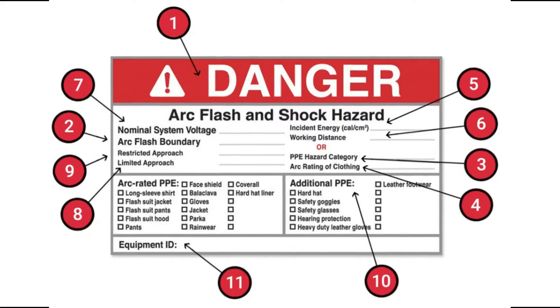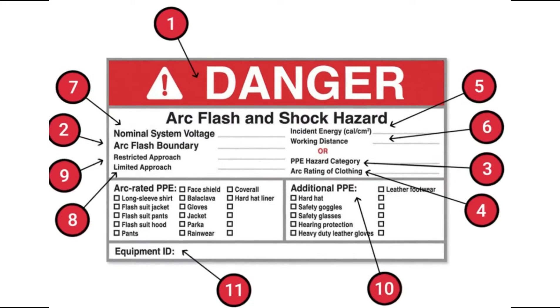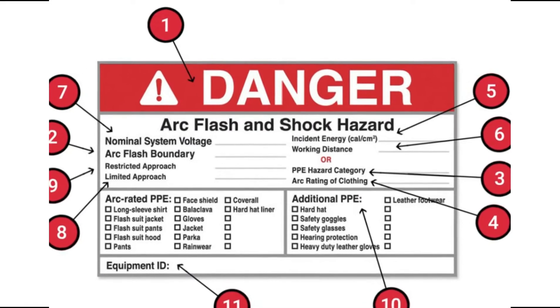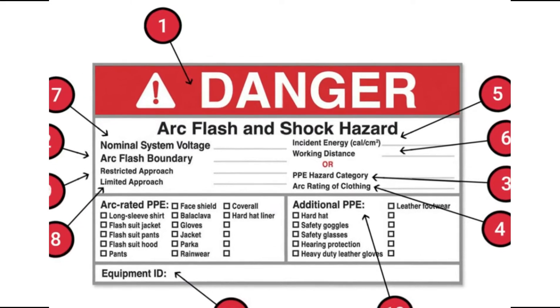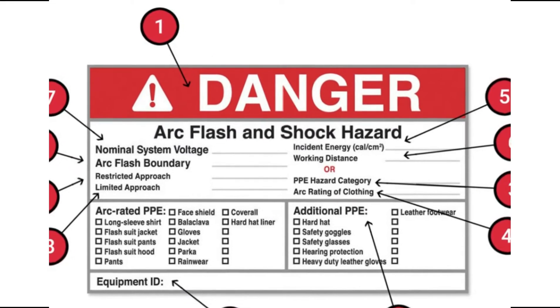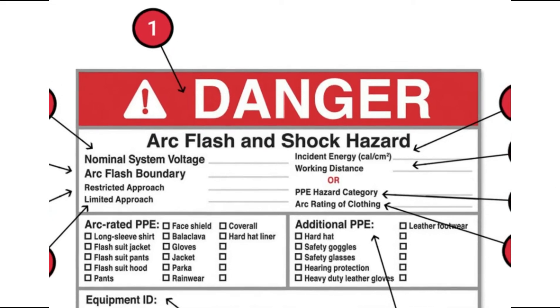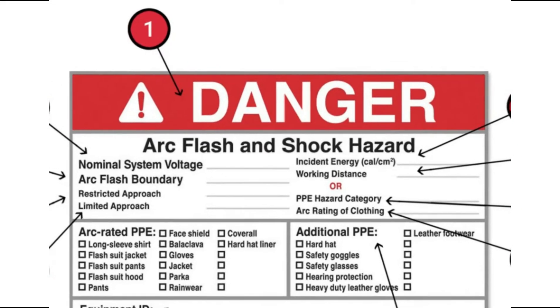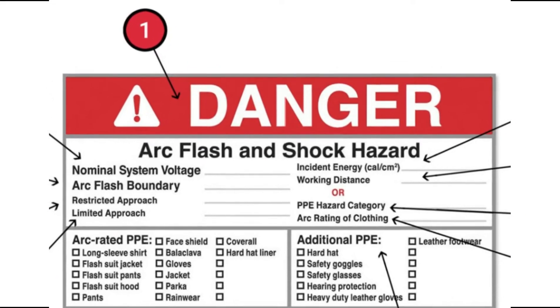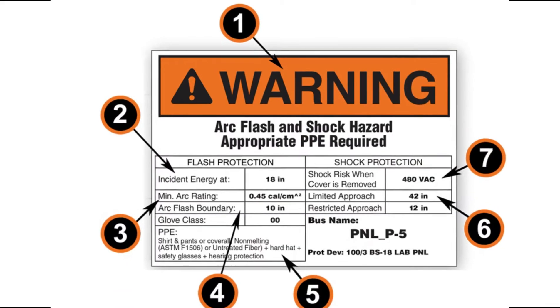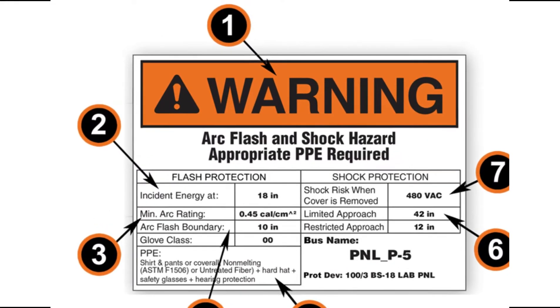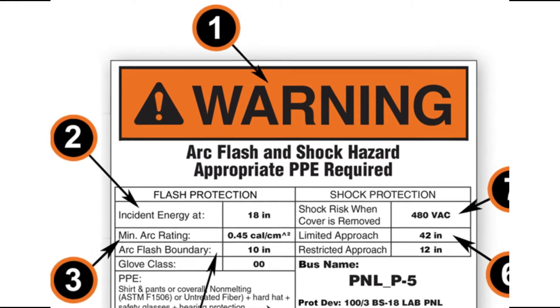The next page shows a breakdown of the arc flash label and the information required. Number one: the danger or warning header. A common guideline is to use a danger header when the voltage is over 600 volts or when the incident energy is over 40 calories per centimeter squared. If it is less than that threshold, an orange warning header is typically used.